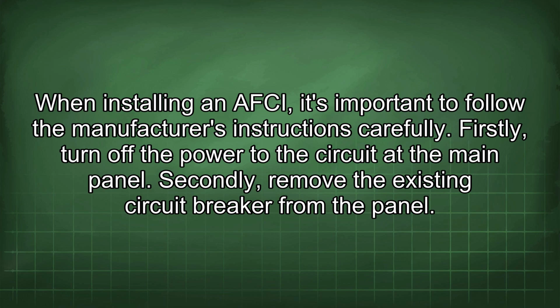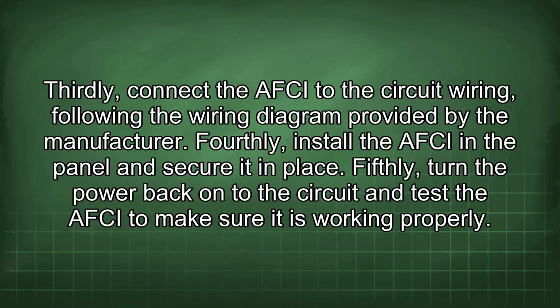When installing an AFCI, it's important to follow the manufacturer's instructions carefully. Firstly, turn off the power to the circuit at the main panel. Secondly, remove the existing circuit breaker from the panel. Thirdly, connect the AFCI to the circuit wiring, following the wiring diagram provided by the manufacturer. Fourthly, install the AFCI in the panel and secure it in place.